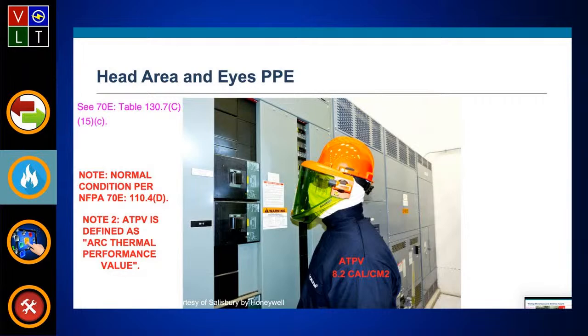This person has an ATPV-type uniform on, 8.2 cal per centimeter squared. If we go to about page 10 of the 70E document, on the left-hand side under arc rating, it explains that ATPV is an arc thermal performance value. The other value is EBT, energy break-open threshold, where energy hitting that uniform could cause it to break open. You're looking at fire resistance as well as arc resistance when you see those values on your equipment, spelled out on page 10 under arc rating.